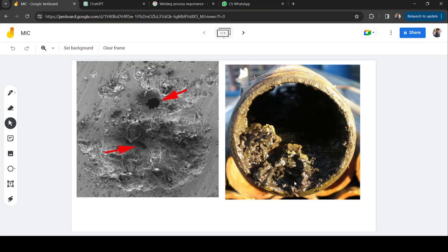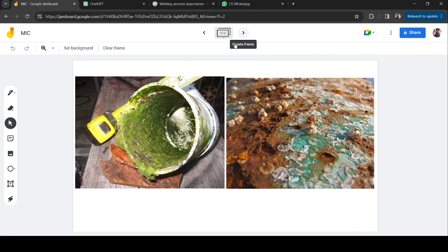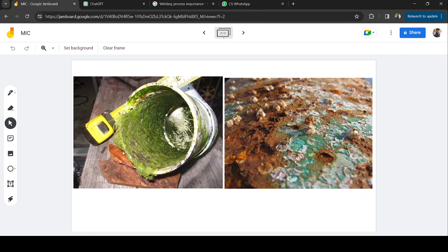This sludge layer, in this you are able to see this colorful appearance. This is algae formation and this is a halo effect that we are able to see. Okay, so these colonies are going to be the microbiology induced damage on the surface.